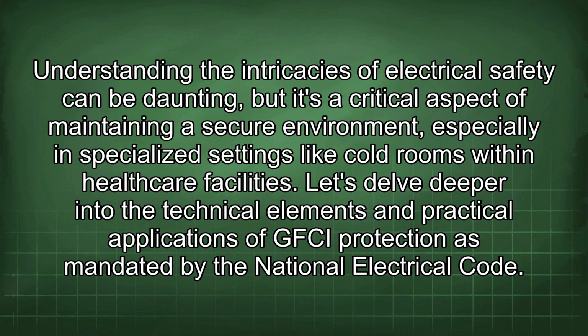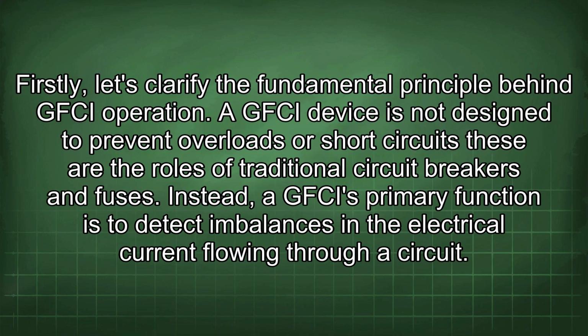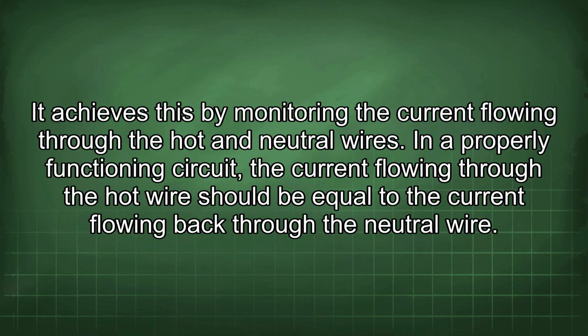Let's delve deeper into the technical elements and practical applications of GFCI protection as mandated by the National Electrical Code. Firstly, let's clarify the fundamental principle behind GFCI operation. A GFCI device is not designed to prevent overloads or short circuits. These are the roles of traditional circuit breakers and fuses. Instead, a GFCI's primary function is to detect imbalances in the electrical current flowing through a circuit. It achieves this by monitoring the current flowing through the hot and neutral wires.